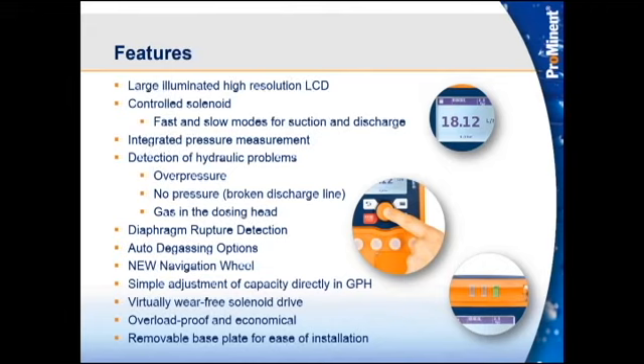Ways to get rid of that air in the head: we have diaphragm rupture. We have auto degassing options for the pump. There's numerous different options available on this Gamma X pump compared to some of our others. If you're familiar with the Delta, again, the only option for auto degassing on that was a rather expensive solenoid option. Okay, that option is also available on the Gamma X, but we also now have the acrylic head with the 3 valves on it, our normal auto degassing that was available for the Gamma L and the Betas. So that head is also available, typically ordered as our NPE 9. If you're familiar with our ident code, that would be the 9 option.